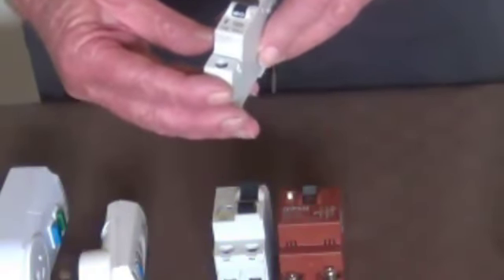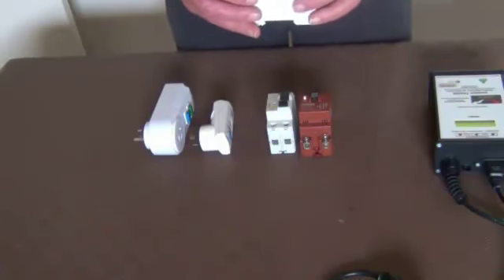Next we have the circuit breaker. A circuit breaker is an overcurrent protection. It is used to protect circuitry, wiring and equipment. It is not to protect people. It does one thing and one thing only. When the current exceeds the rating, this one, I can't see a rating on it, probably 10 amps or 15 amps, 20 amps, sorry. Once it exceeds that, it will trip and open the circuit. That's all they do. You can't test them, and they don't have a test button.